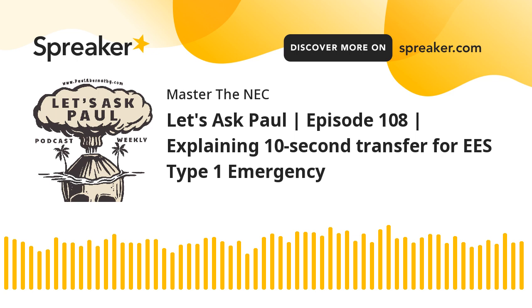Now, remember, it could be less than 10 seconds if the AHJ determines that it needs to be for whatever reason, and most of them will not. They won't get involved in that, okay? They just follow the rule where it says within 10 seconds, as we follow it when we're looking at Article 700. So, interesting thing about 517, there are some areas in 517 that don't have to be in accordance with Article 700, and it'll tell you that.